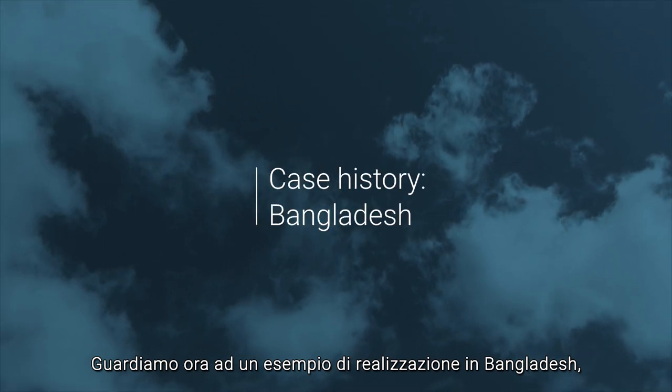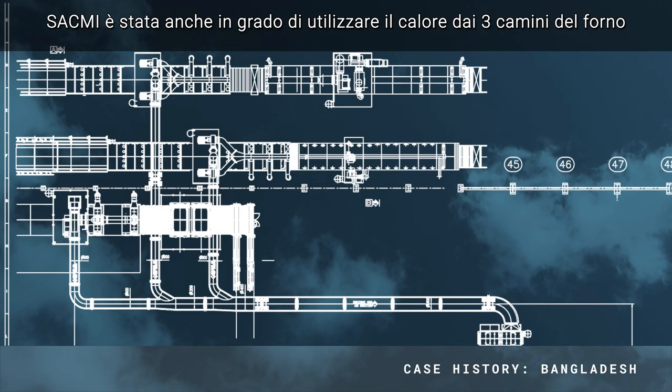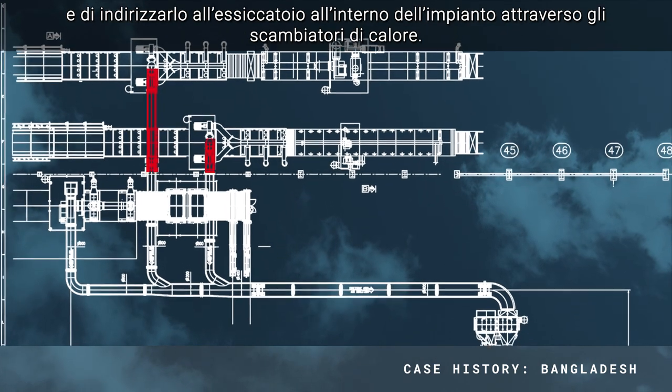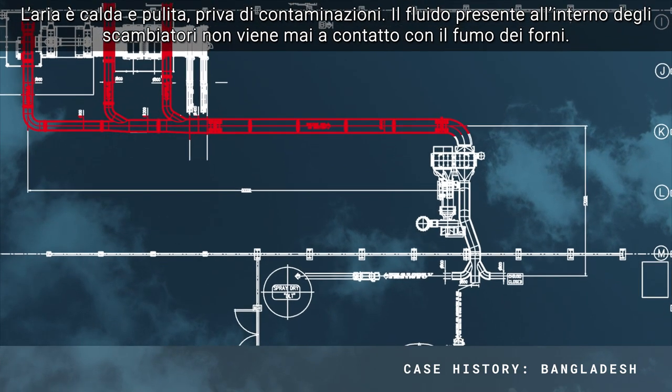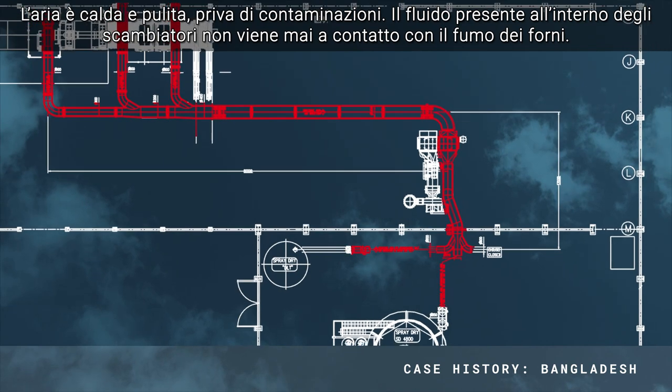Let's take a look at an energy efficiency implementation in a ceramic plant in Bangladesh. These efficiency solutions were implemented on an existing plant and adapted to the specific needs of both the market and the customer. SACMI was able to utilize the heat from the 3 kiln chimneys and direct it to a spray dryer in the plant via a heat exchanger. The air is hot and clean, without contamination — the fluid never comes into contact with the kiln smoke.